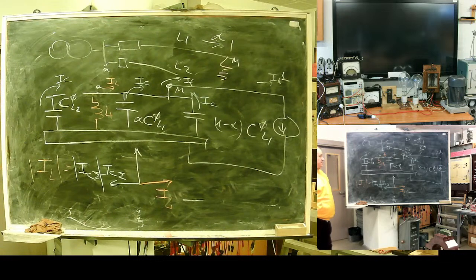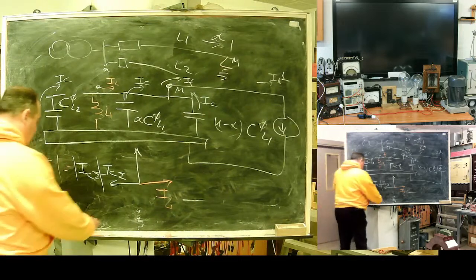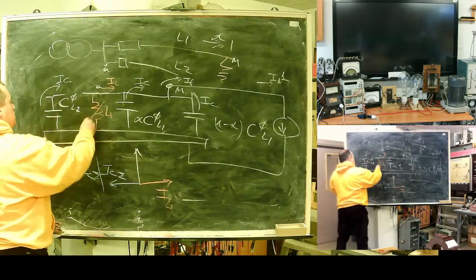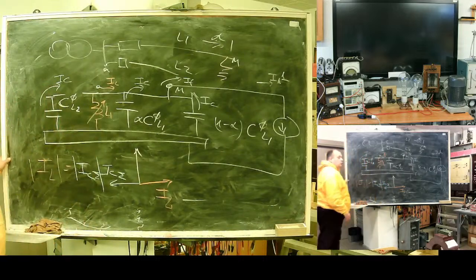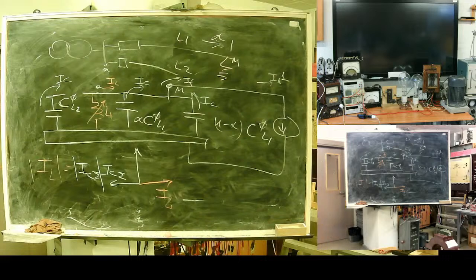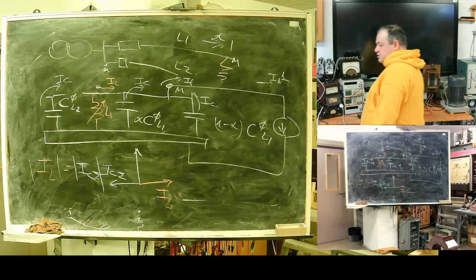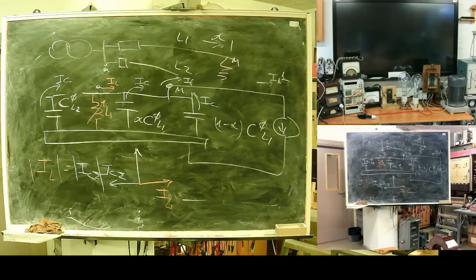This thing is called resonant network or resonant neutral. Better use this term, resonant neutral. Petersen invented this. So this coil is often called a Petersen coil. With the help of Petersen coil, I can reduce fault current to 0.